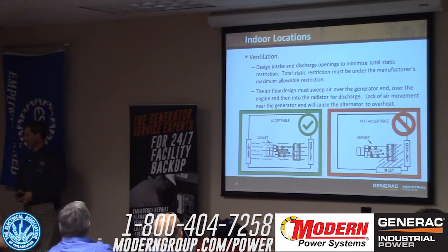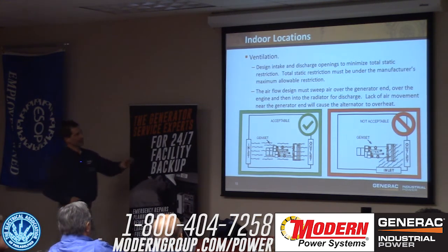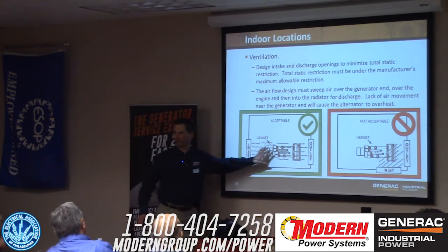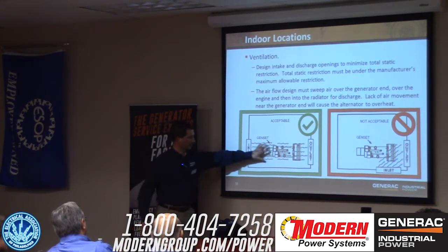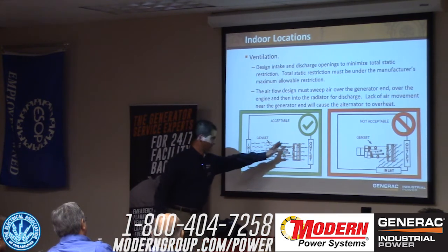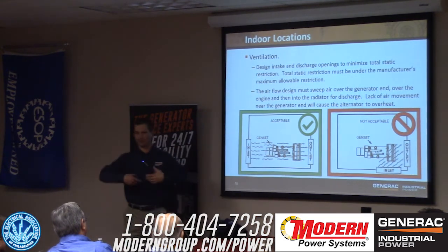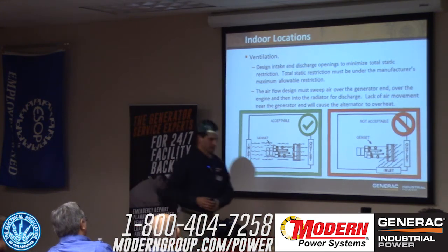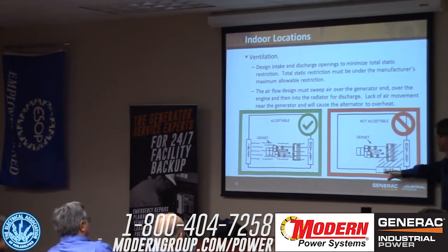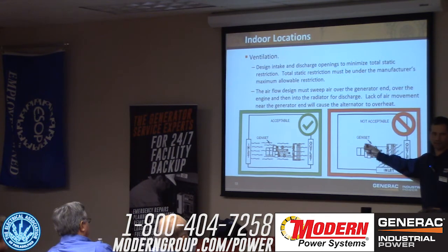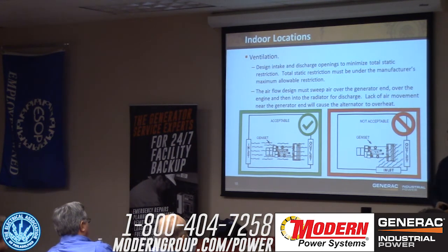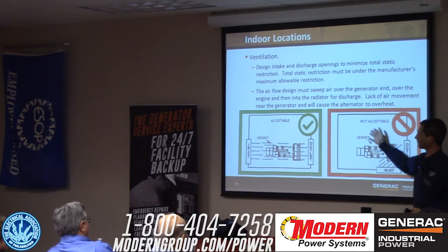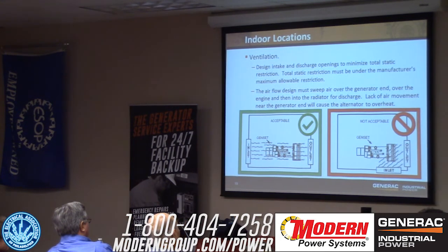We look a little bit again at ventilation. If I'm going inside, ideally this is kind of the airflow pattern that I want. I've got to get air moving across that alternator because there's a fair amount of waste heat coming off of that as well. I've got to pull across the generator itself or the engine itself, and then finally it's going to hit the radiator and out it goes. If I were to do something like this, I'm going to end up overheating back here. I'm not going to be able to reject the heat from the alternator effectively. This whole backside of the room is going to start to get a little bit warm, and you're going to start to have issues. All right.